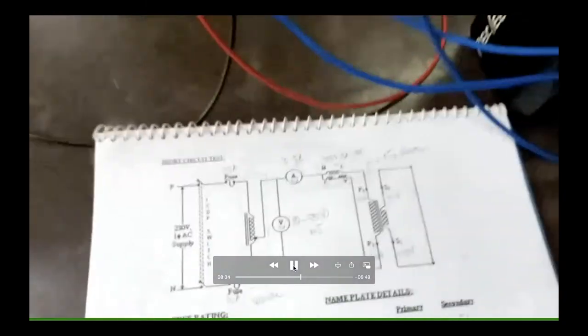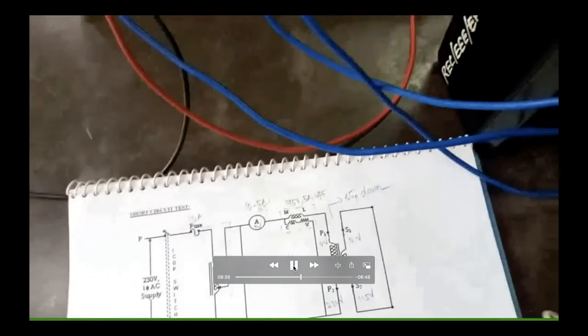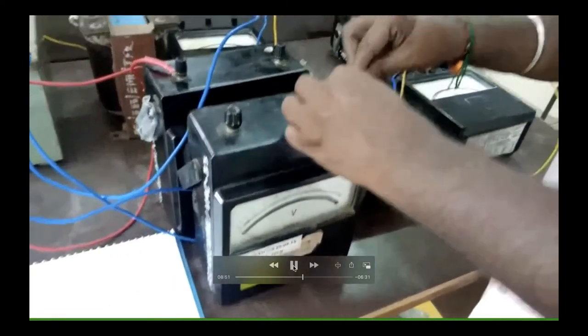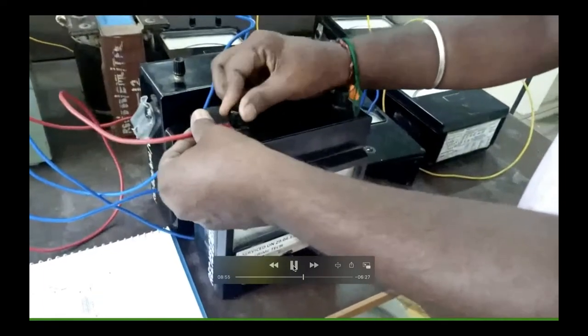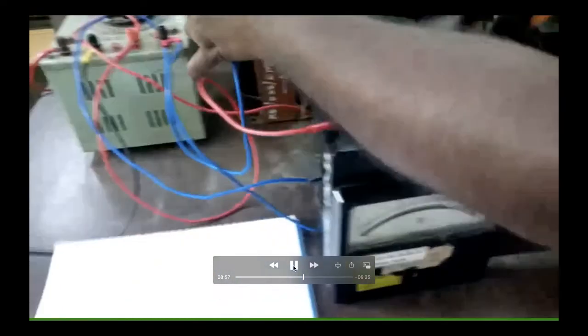So you have to take 75 volt voltmeter, 5 amps ammeter, and the wattmeter is also being changed, LPF and UPF wattmeter, and you need to change the position of the winding of primary and secondary. That is much more vital, because we need to short only on the low voltage side rather than the high voltage side to prevent any fault in the transformer.